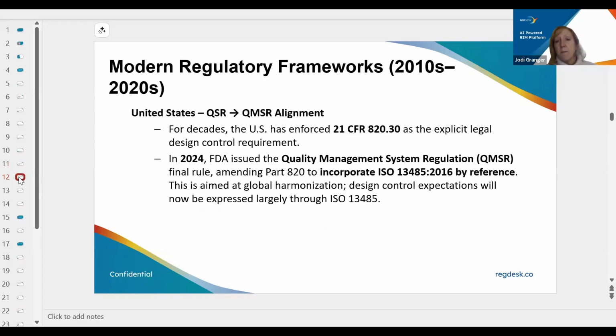In the US, one major change that is being made: for decades, the US enforced 21 CFR 820, and that was the explicit legal design control requirement. In 2024, FDA issued the QMSR regulation, the final rule, which is going into effect. And this is essentially incorporating the ISO 13485 used in Europe by reference to the law.